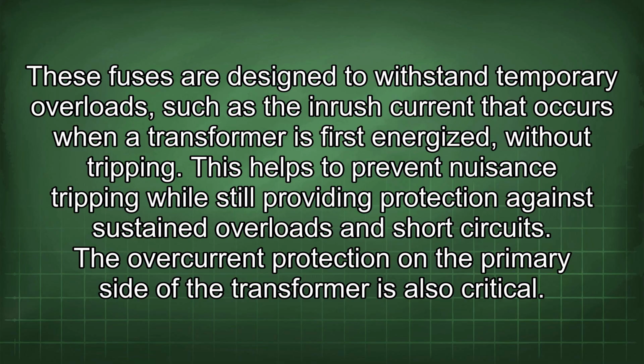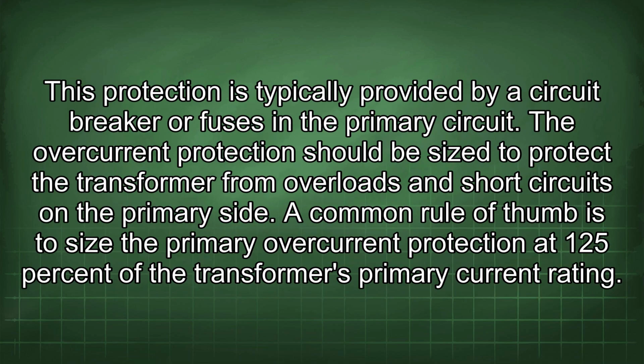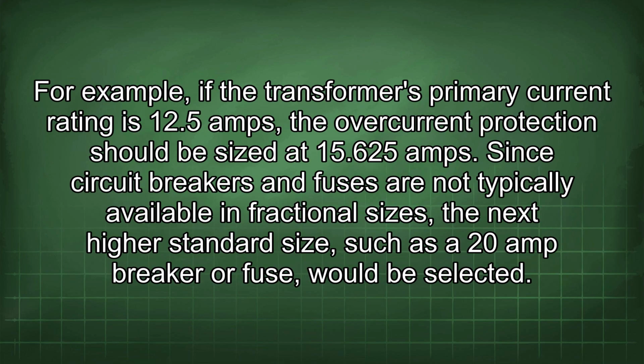The overcurrent protection on the primary side of the transformer is also critical. This protection is typically provided by a circuit breaker or fuses in the primary circuit. The overcurrent protection should be sized to protect the transformer from overloads and short circuits in the primary side. A common rule of thumb is to size the primary overcurrent protection at 125% of the transformer's primary current rating. For example, if the transformer's primary current rating is 12.5 amps, the overcurrent protection should be sized at 15.625 amps. Since circuit breakers and fuses are not typically available in fractional sizes, the next higher standard size, such as a 20 amp breaker or fuse, would be selected.